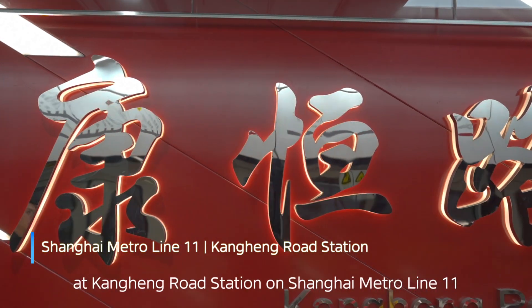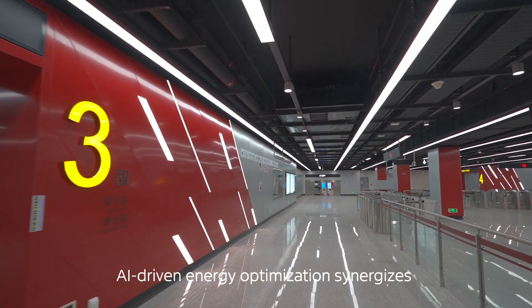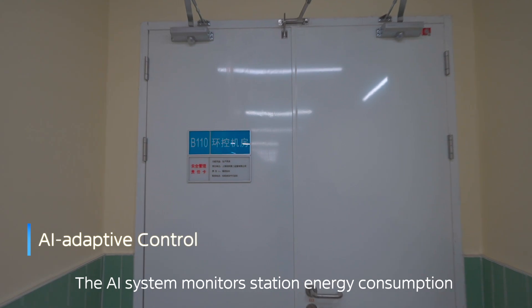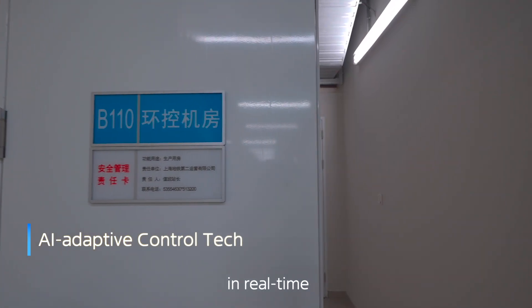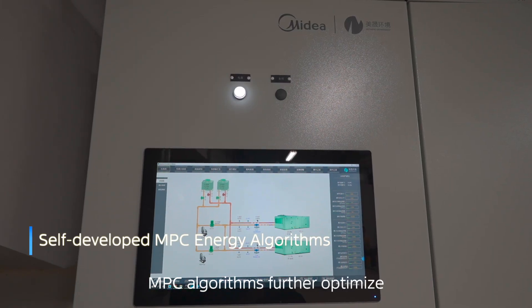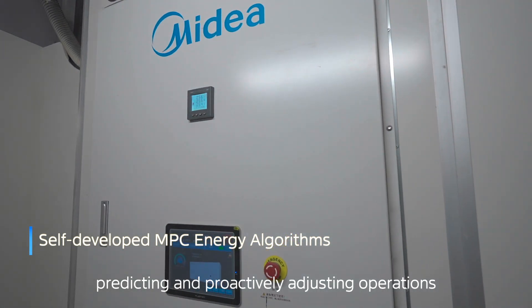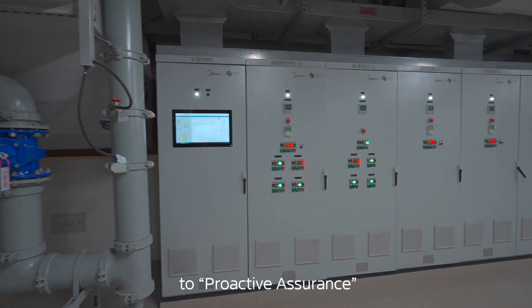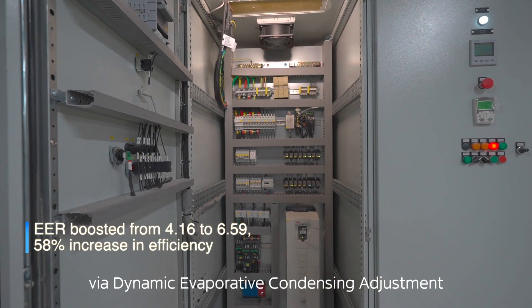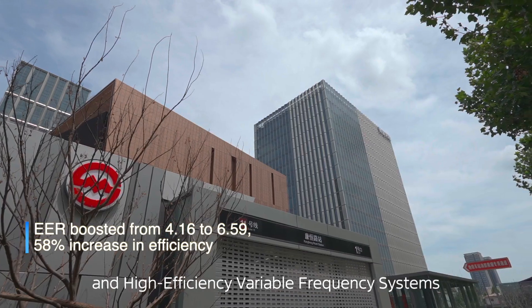Simultaneously, at Kangheng Road Station on Shanghai Metro Line 11 — the first retrofit project on an existing line — AI-driven energy optimization synergizes with MPC algorithms. The AI system monitors station energy consumption in real-time, dynamically adjusting HVAC operations. MPC algorithms further optimize temperature and humidity control, predicting and proactively adjusting operations, shifting from reactive response to proactive assurance, achieving industry-beating annual EER via dynamic evaporative condensing adjustment, intelligent control algorithms, and high-efficiency variable frequency systems.